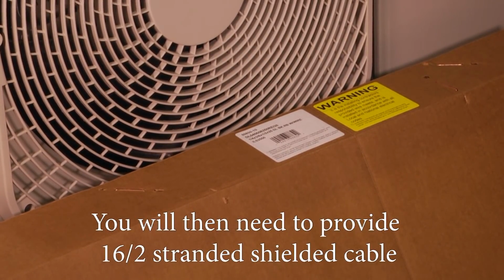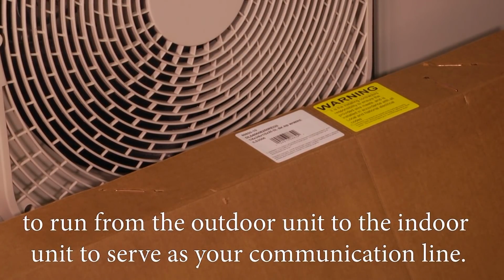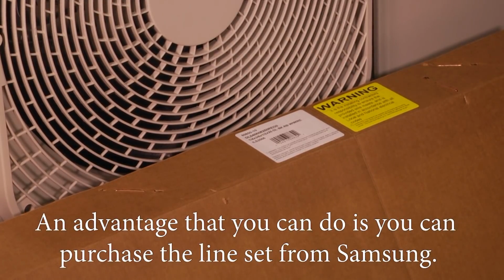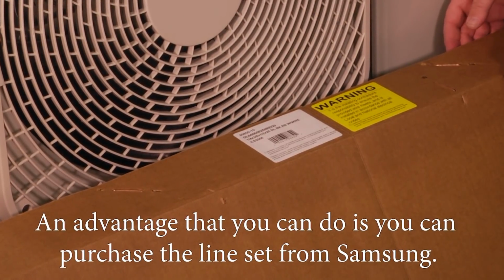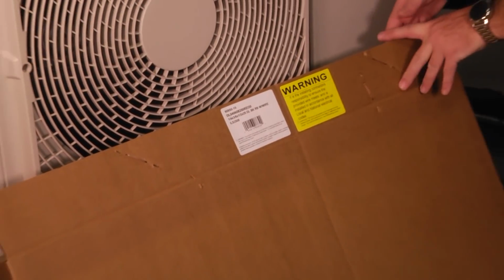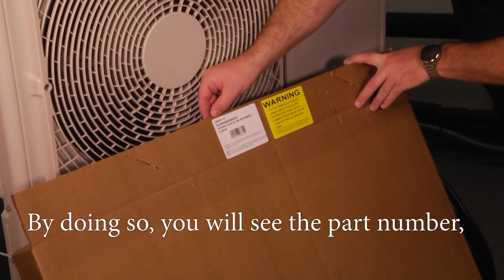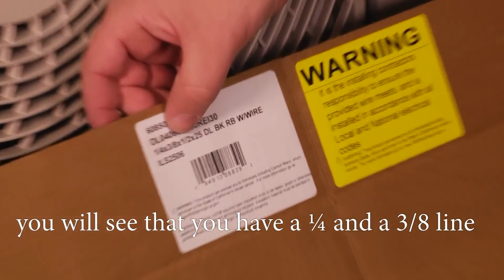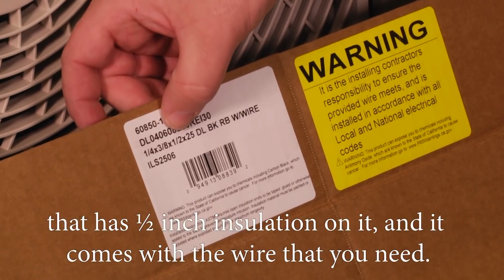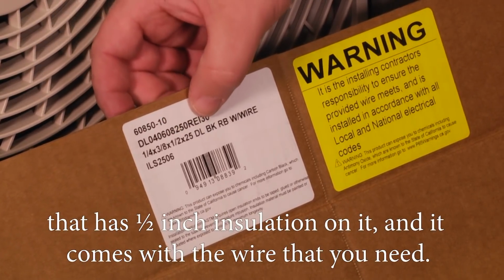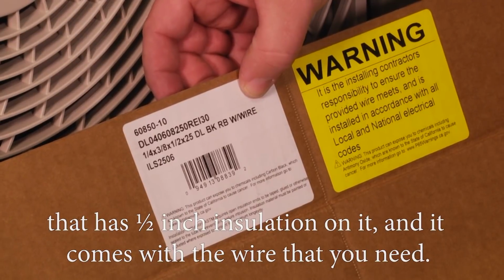You will then need to provide 16-2 stranded shielded cable to run from the outdoor unit to the indoor unit to serve as your communication line. An advantage that you can do is you can purchase the line set from Samsung. By doing so, you'll see the part number, you'll see that you have a 1/4 and a 3/8 line that's got 1/2 inch insulation on it, and it comes with the wire that you need.